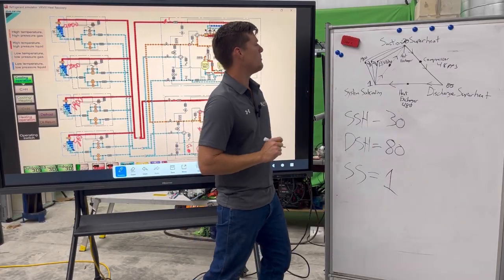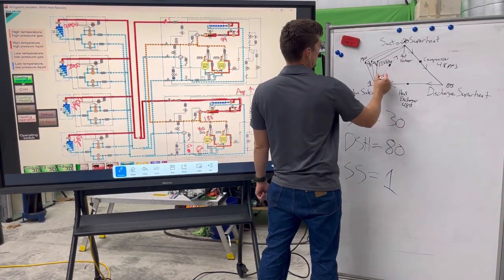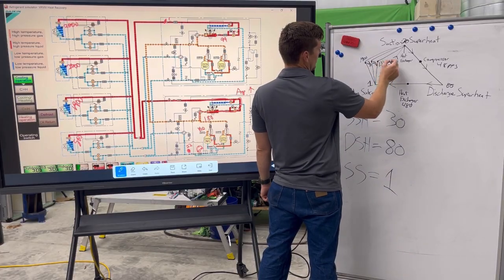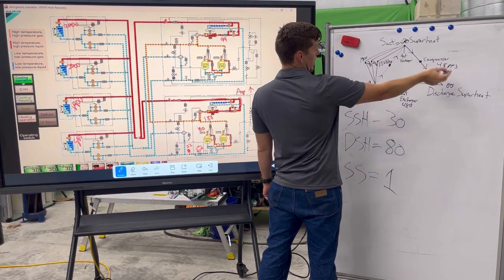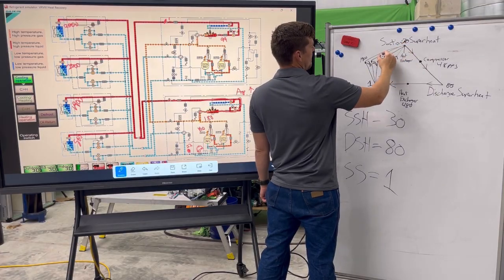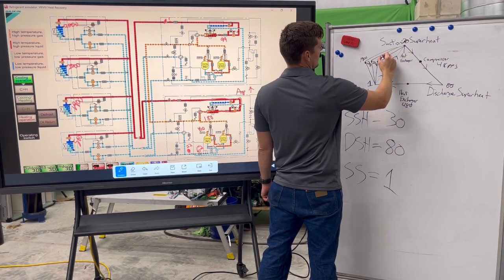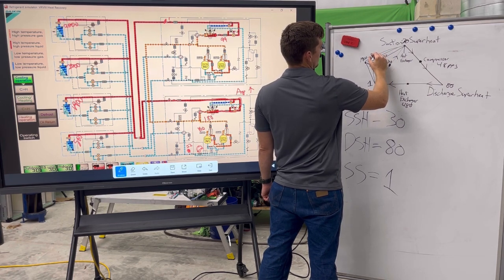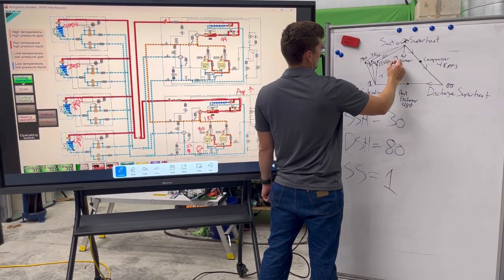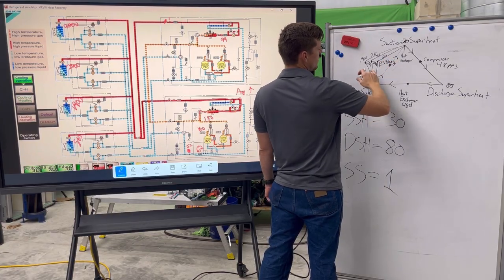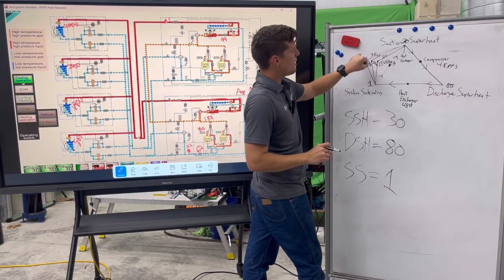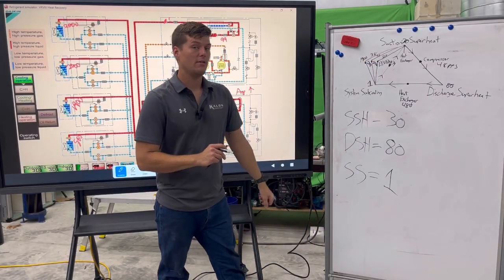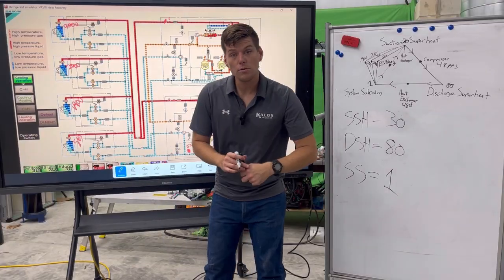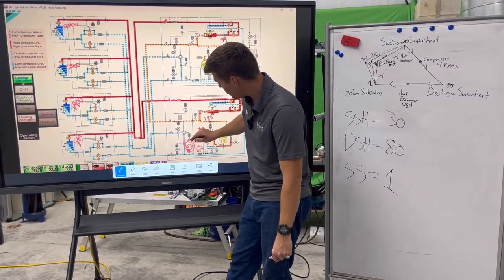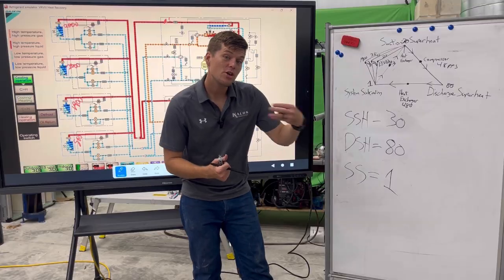So I've got my expansion valves here on my triangle, and I can start adding things like, okay, so we know on this side where our liquid temp is coming in, and this is our indoor heat exchanger on the top of the triangle. Let's say here this is 37, 38, and then this one here, let's say 34. This is my low pressure saturated vapor after my expansion valve, and it's pretty cold. Well, of course it's cold, because when we look over here, we have a 32 degree saturation temperature leaving your expansion valve.